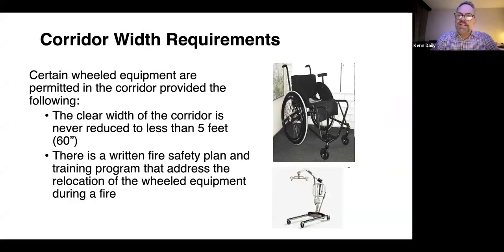Corridor width, of course, again, clear corridors. I don't want anything in the corridors. There should be nothing in there, but they do permit lift equipment and wheelchairs or transportation equipment, as long as you never block enough to leave. You have to leave at least 60 inches. So that's why it's really important to know your corridor widths, because some of you probably don't have wide enough corridors to store stuff in. But you cannot store things in there that block and leave less than 60 inches or 5 feet across your hallway.